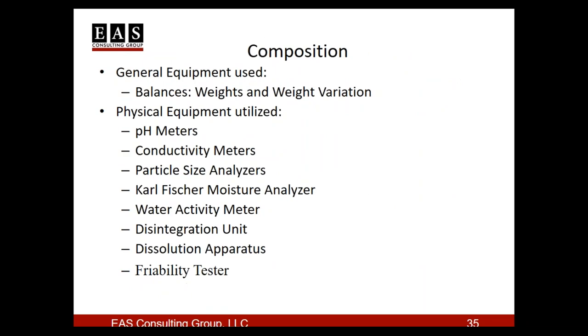For composition, these tend to be the physical parameters being assessed. This includes balances for weight and weight variation, physical tests like pH for liquids, particle size analysis for powders, and density for powders. Moisture content can also be very important, measured by water activity, loss on drying, or a Karl Fischer moisture analyzer.